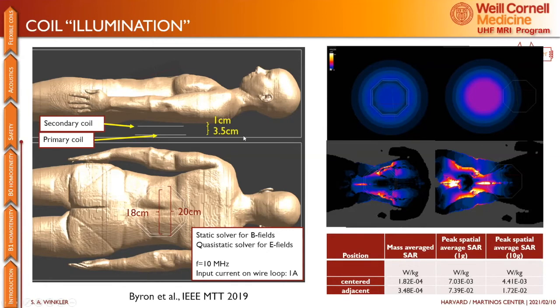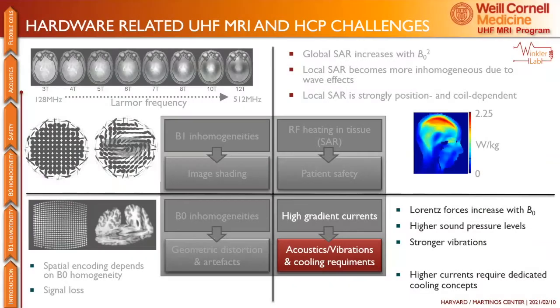I don't want to waste too much time on this, but you can see as the two coils are directly above one another, a lot of energy is transferred, so the SAR is low. As the coils are more adjacent, more of the energy goes into the body, but both situations are safe. This brings me to the last quadrant, which is about the gradients.